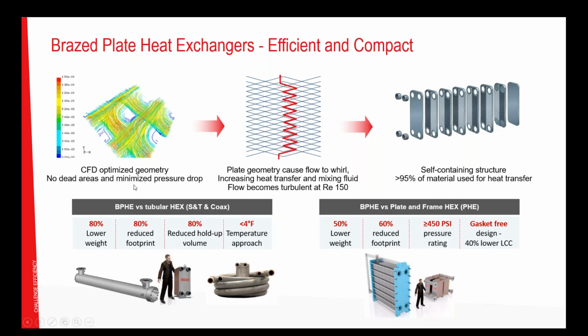In plate type heat exchangers, and especially SWEP, we're using CFD and other methods to optimize the plate design to make sure that it's as efficient as possible. As I showed you in detail before, we have different types of plate technologies creating geometries for optimizing thermal efficiency and pressure drop. And especially in the plate heat exchangers, since the flow is so twirling, we get a turbulent flow already at Reynolds 150, which is very, very low if you compare it to about 2,300 in a straight tube of the shell and tube.